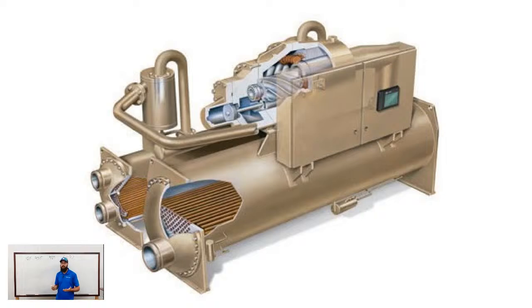What that effectively does is lower our ability to cool the water down, and we're pulling less refrigerant off of the evaporator. So when we're moving less refrigerant volume, obviously we're going to move less BTUs. At that point, our goal is to lock in at that set point with as precise control as we can have and just cruise right there. And keep in mind, when you're dealing with chillers, it's not like a regular RTU or any other system. They should never have to cycle, especially when you start dealing with screw or centrifugal machines.